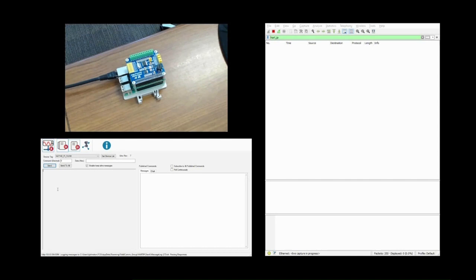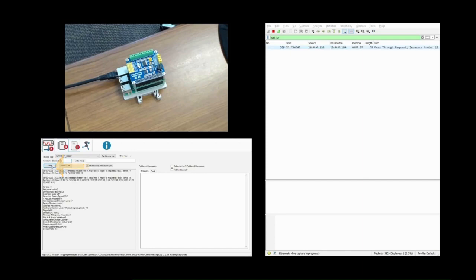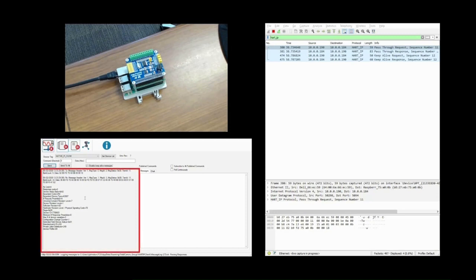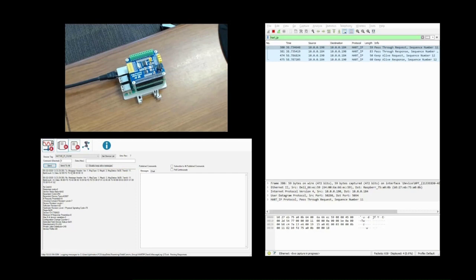This device implements all the universal and common practice commands required by HART IP. We begin by sending command zero. Just enter the command number and data here — you don't need to enter the byte count, the client takes care of that. Click send and the command is sent. Looking at Wireshark, you can see the communication on the wire. Wireshark has filtering capabilities; for this demo, we have the filter set to only show HART IP traffic. The command request and response is shown on the client, which knows this command and decodes it for you. This also shows how fast HART IP is — the request is sent and the response received with about a one millisecond turnaround.